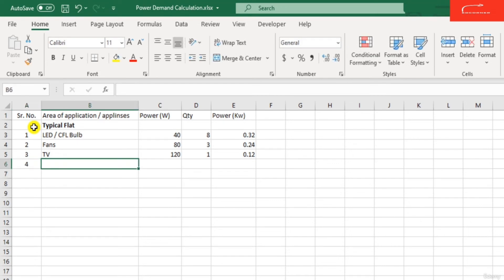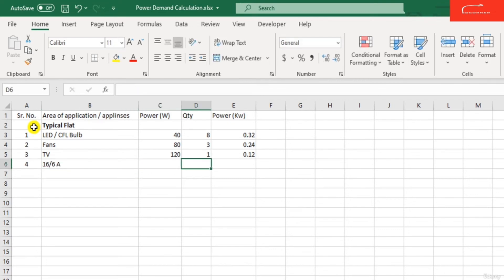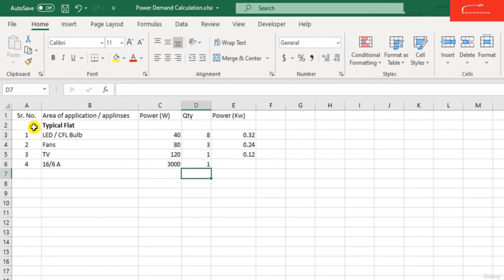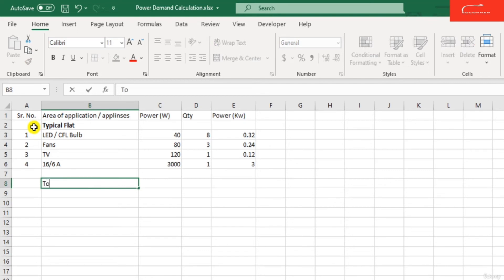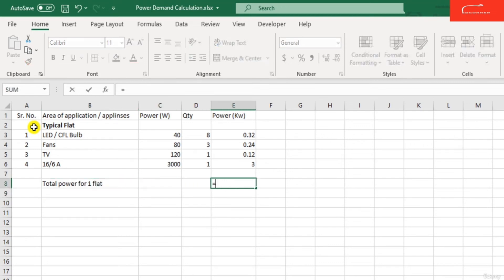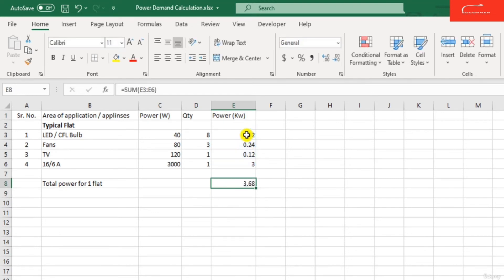For any supply — for example, 6 by 16 ampere connections — the power generated by the 6 by 16 ampere socket is around 3000 watts, quantity 1, so it will be around 3 kilowatt. The total power for 1 flat is around 3.68 kilowatt. This is the total power required per flat in case of emergency.